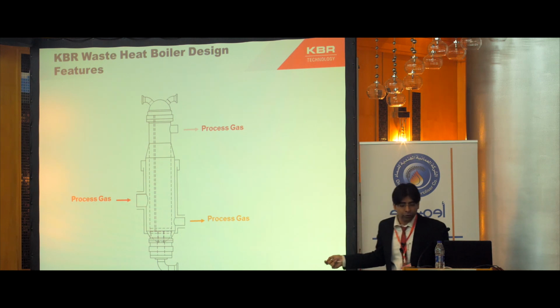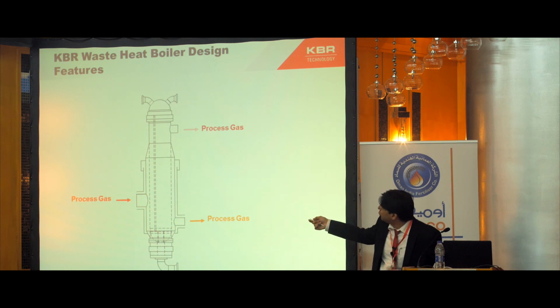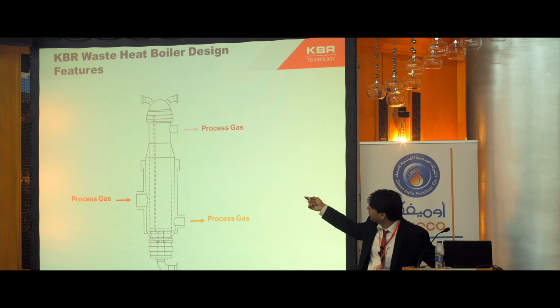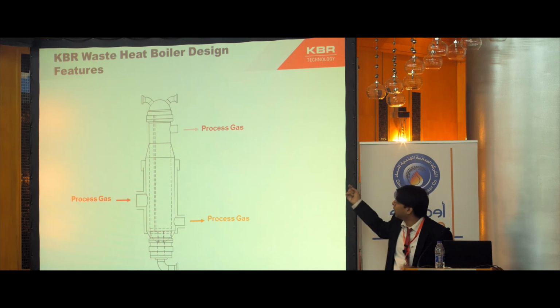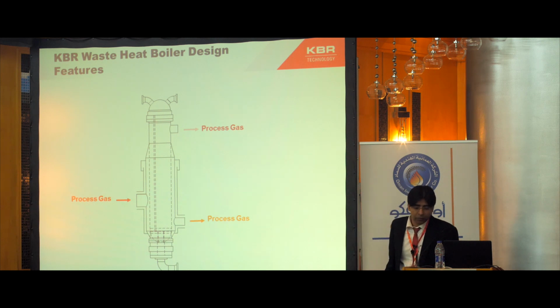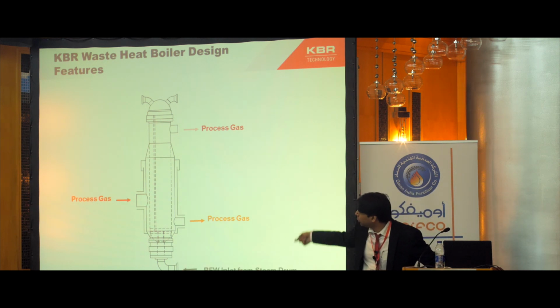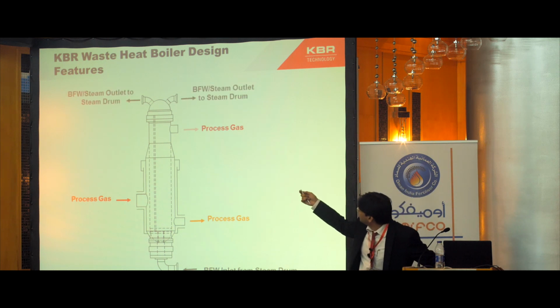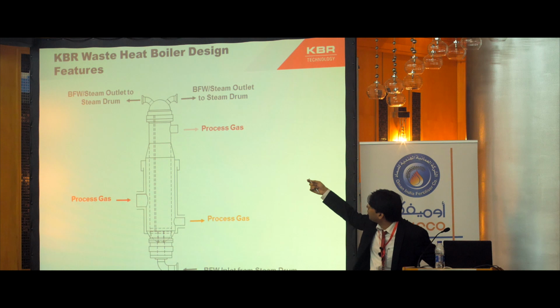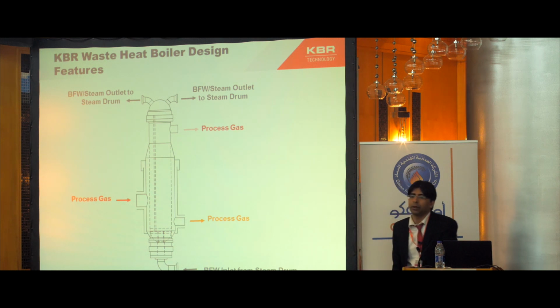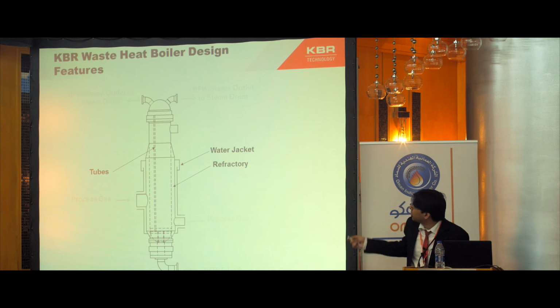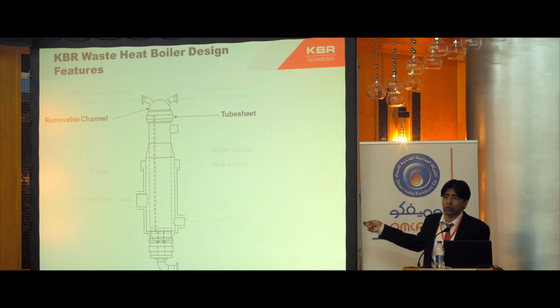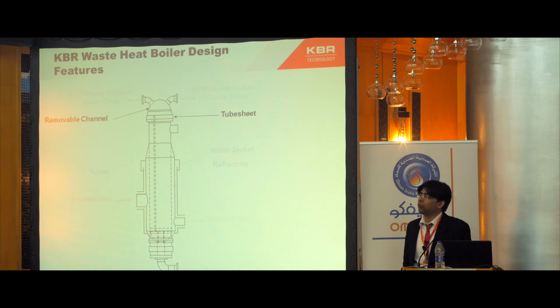The process gas comes from the side, and it is unequally distributed between the two ends to control the temperature out of the inlet to the HTS. The boiler feed water comes from the bottom through the downcomer from the steam drum, and there are risers which are connected to the steam drum from the top of this boiler. The shell is still protected by a water jacket, but this time instead of metal liner, we have provided dual layer refractory. One layer is used for heat conservation, and the second layer is used for erosion protection.